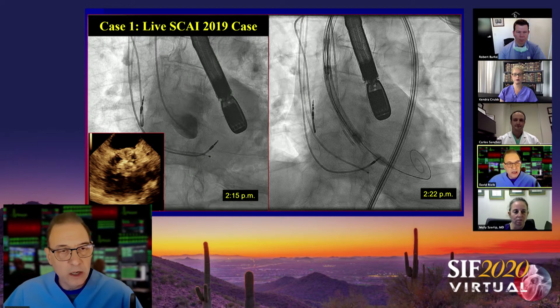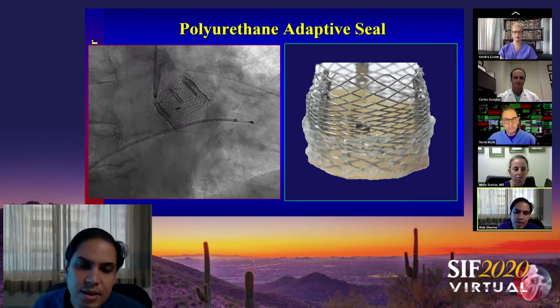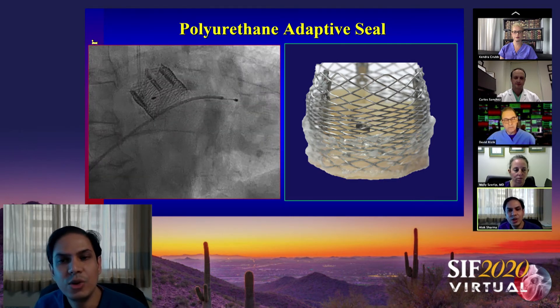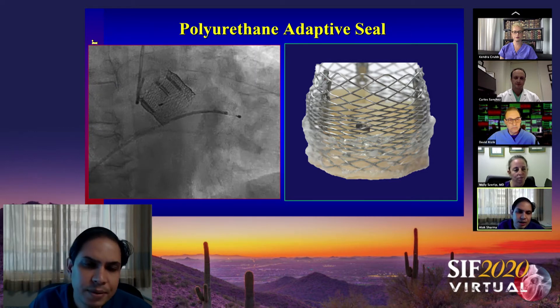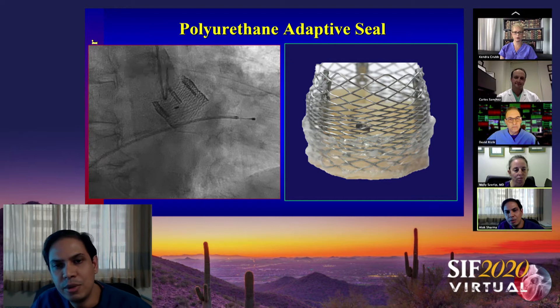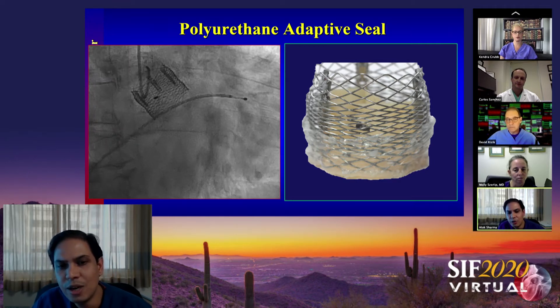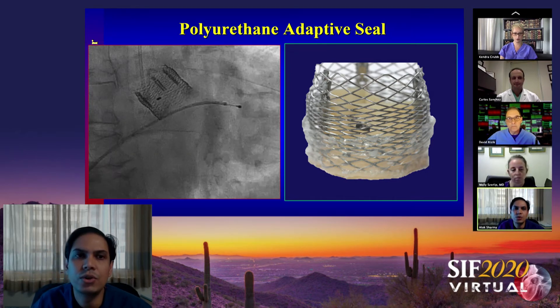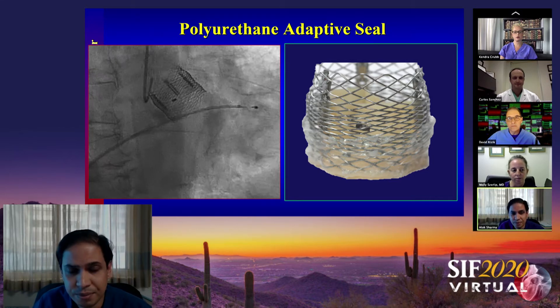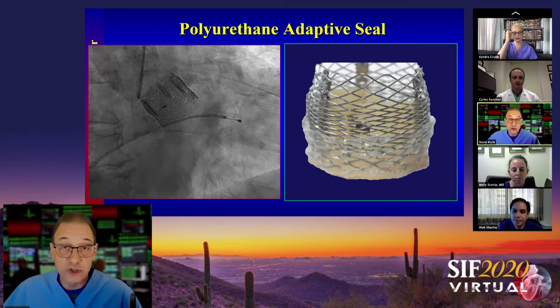Regarding the polyurethane adaptive seal — Dr. Sharma, talk to us about it. We all know that moderate to severe paravalvular leak is associated with increased mortality. The adaptive seal is a unique feature of the Lotus valve. As the valve is deployed, it fills the gap between the annulus and the valve with a multi-layer polymer structure, virtually eliminating paravalvular leak. In the REPRISE III trial, the rates of paravalvular leak were seven times lower compared to the CoreValve or Evolut R — less than 1%, specifically 0.7% at three years.